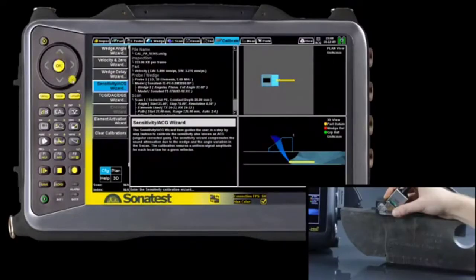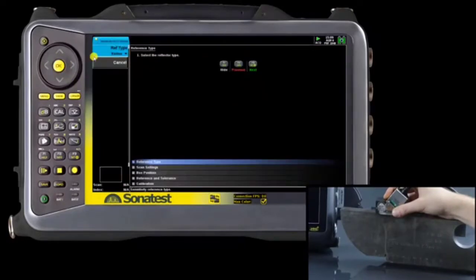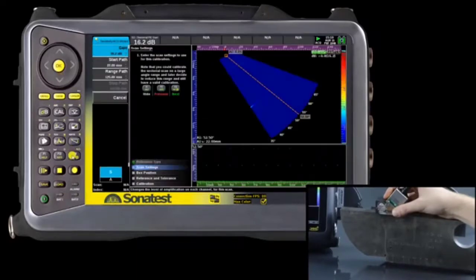We are still in the same setup as the previous calibration video, and we are going to select the sensitivity wizard. As a reference reflector, you can choose from 3 different kinds of geometry, either a radius, a thickness or a side drilled hole. For this calibration block, we will be using the radius geometry. To make the calibration easier, we suggest you put the signal amplitude slightly under the reference level.